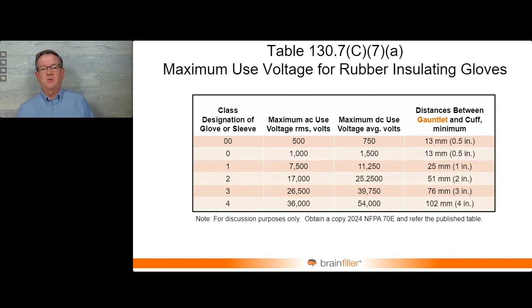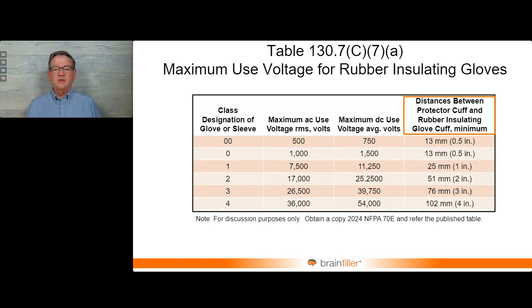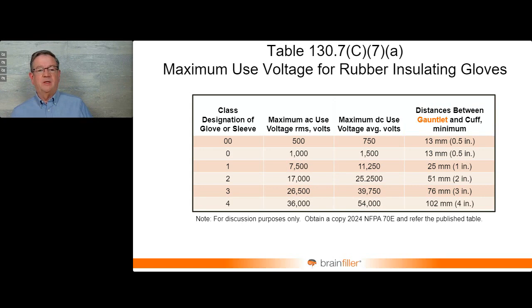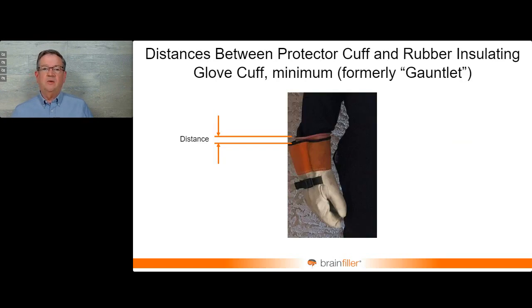Instead of distance between gauntlet and cuff, add more words. Distance between the protector cuff and the rubber insulating glove, minimum. And why you have to have a minimum distance is because you have to be able to visually see that the insulated glove is there. If the insulated glove was down in the protector, you wouldn't know where your electrical insulation ends. So it extends beyond the protector just a little bit.